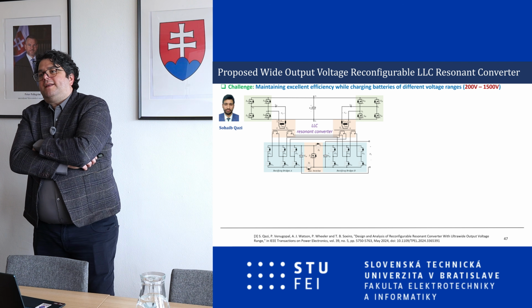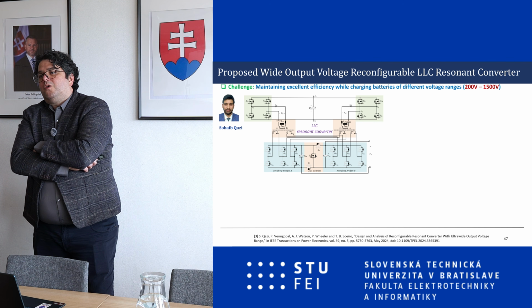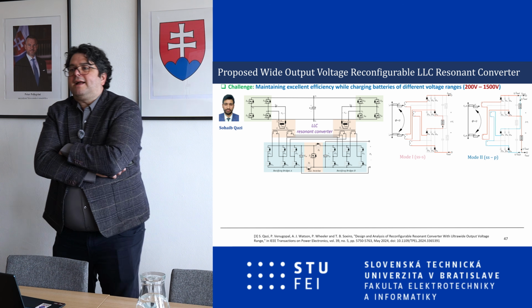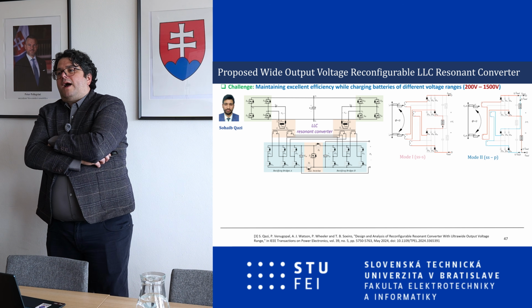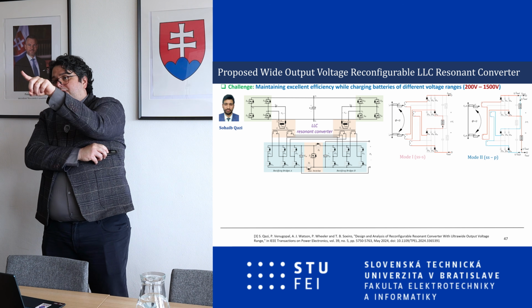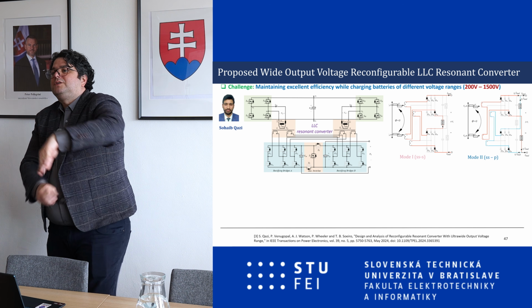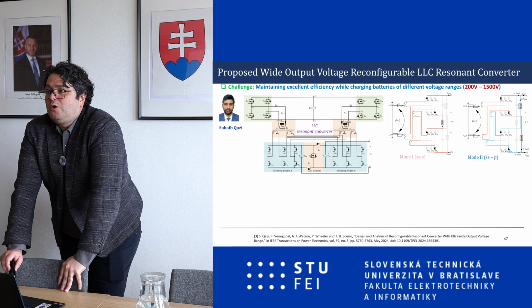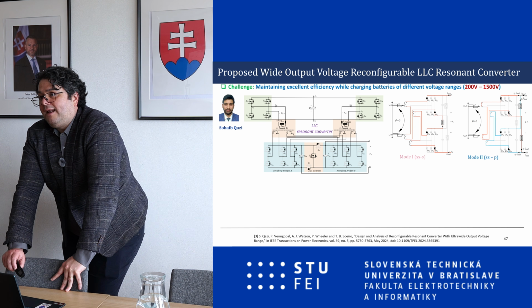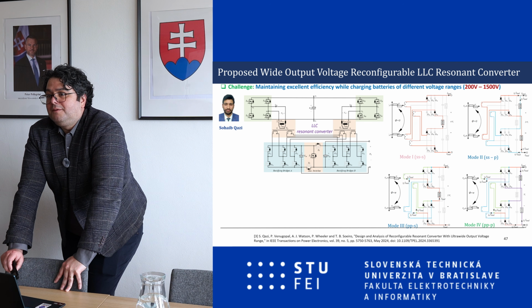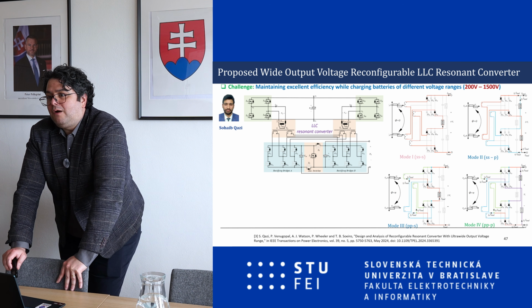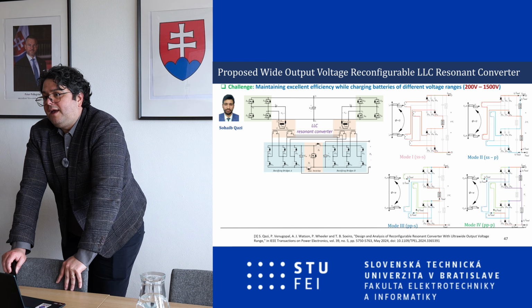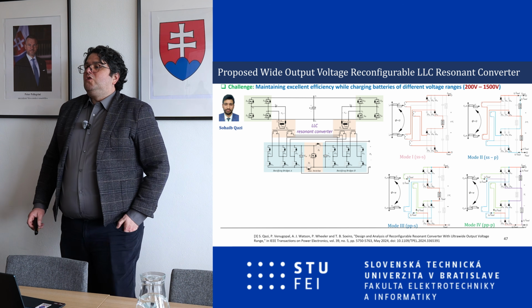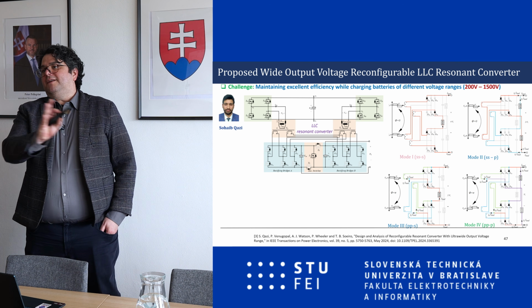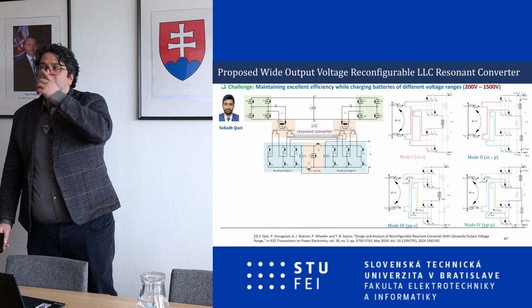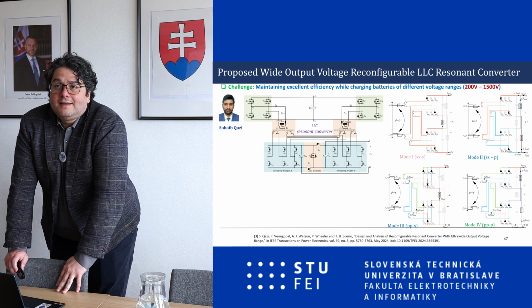We did this with a 4-winding transformer. We can now do different configurations - connect all the secondary windings in parallel or in series. In the first case, all transformers in series, giving a large voltage gain. You can connect 2 windings in series, connected in parallel, in mode 2. Mode 3 has them in parallel and in series, and mode 4 has all of them in parallel. Independent of which mode you're in, the utilization on the primary side stays the same, so we fully utilize the transformer and the devices.